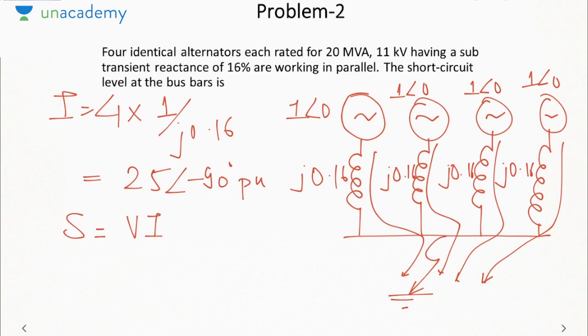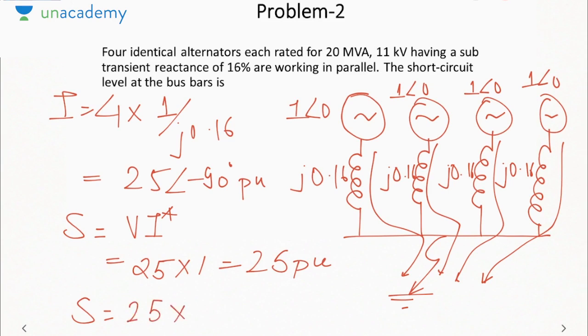Now S will be V I conjugate. So it will be 25 into 1, that is 25 pu. So in actual value it will be 25 pu into base. Base is 20 MVA, so it will be 500 MVA. This is the short circuit level at the bus bars. So remember, in case of a three-phase short circuit fault, the per unit value of fault current is the same as the per unit value of short circuit MVA, because the voltage at no load is equal to 1 angle 0, which is equal to the rated voltage. So we can directly say per unit MVA is the same as the per unit fault current.